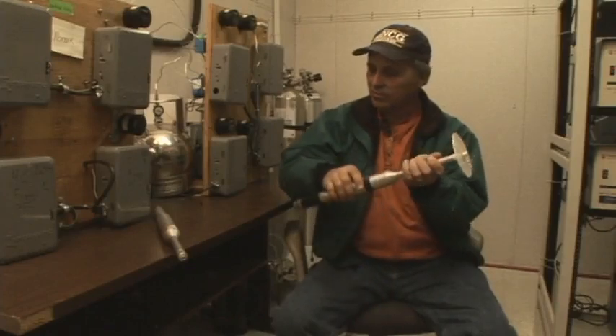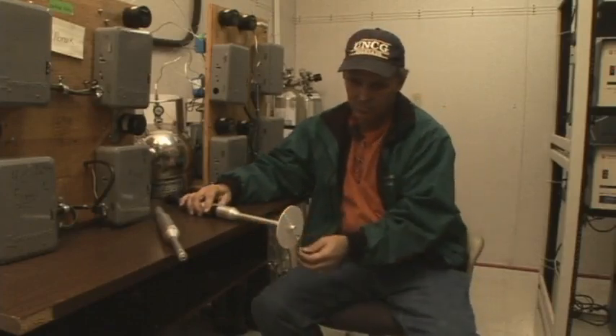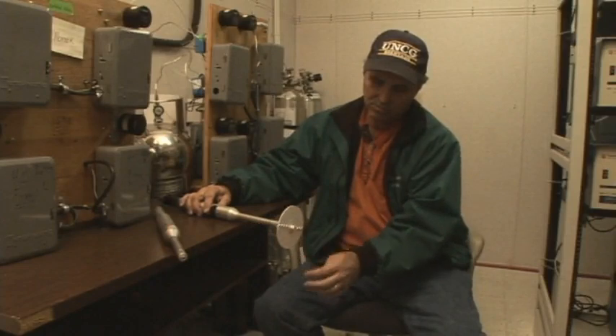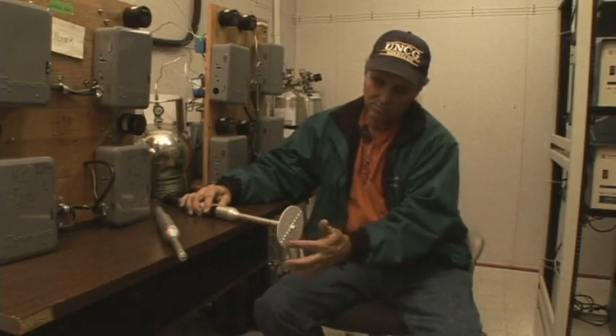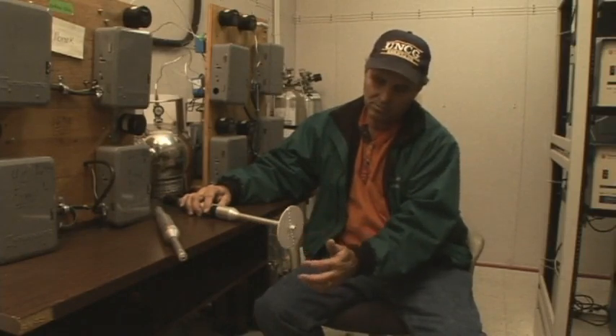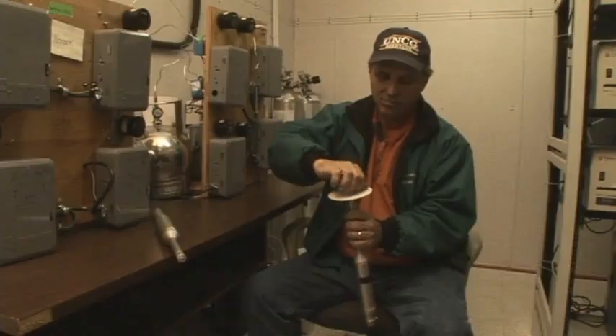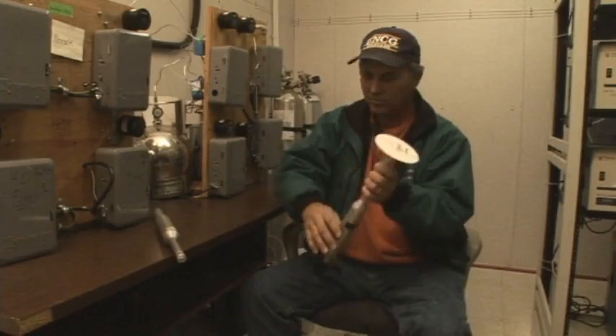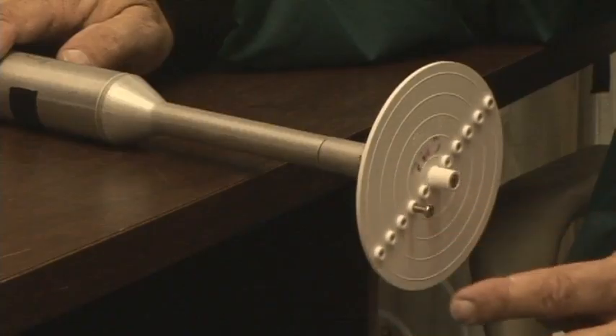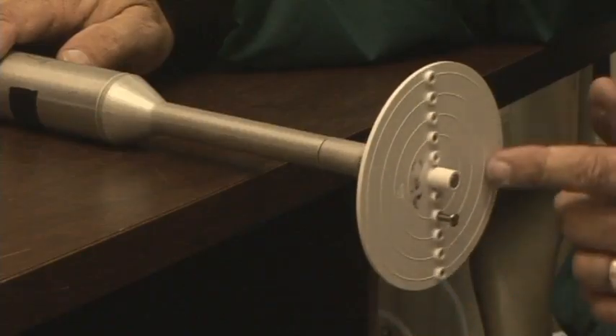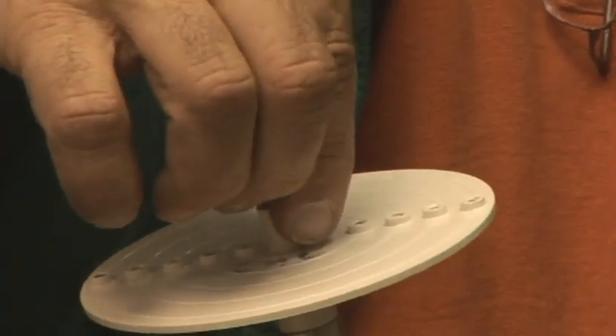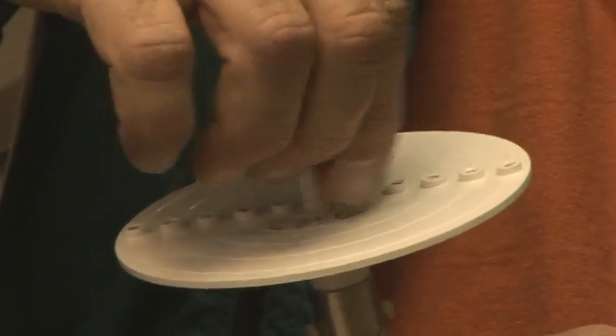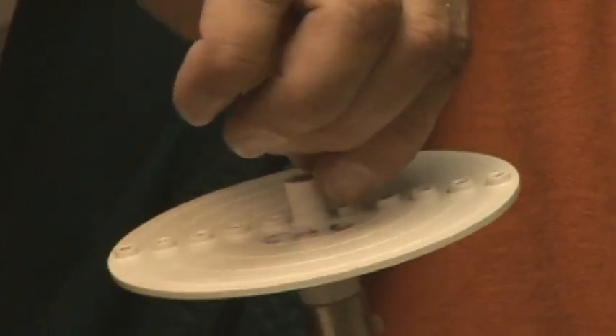The technician holds the wheel so that the screw is parallel to the table. When the technician lets the wheel go, if the wheel moves, then the torque is less than 3 gram-centimeters. Now move the screw to the hole that is the number 2 position. Repeat the test. If the wheel moves in the number 2 position, then move the screw to the number 1 position. If the wheel moves in this position, then record the torque as 1 gram-centimeter.